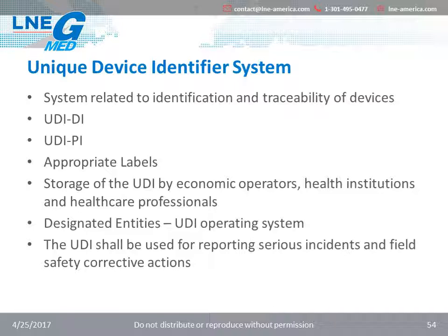Member states may also require health institutions and professionals to store UDIs of the devices that they have been supplied with as well. One or several entities will be designated to operate a system for assignment of the UDIs, and we'll provide more information on these entities either through client bulletins, newsletters, or future webinars as it becomes available. But the most important thing to remember is that the UDI has to be used for reporting serious incidents and any field safety corrective actions.